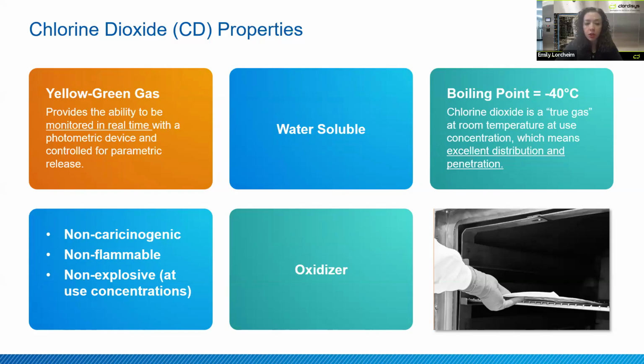Chlorine dioxide is also non-carcinogenic, non-flammable, and non-explosive at use concentrations. So those are key things when looking at an ethylene oxide alternative. Ethylene oxide is facing a lot of environmental issues right now, mostly the carcinogenic aspect of it, both with emissions and its residuals. And because chlorine dioxide is not explosive, we're able to sterilize things with embedded batteries, as well as other sensitive electronics. A difference is that it is an oxidizer. Now, most of the alternative sterilization methods are oxidizers. However, chlorine dioxide is the most compatible with materials of the oxidizers out there.